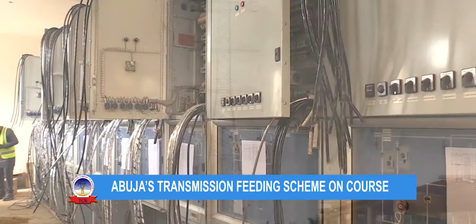An assistant manager at the AIFDPIU of TCN, Engineer Mohammed Zubairu, gave an overview of the Gwarimpa gas-insulated substation project, which he supervises. The station is 2 by 60 MVA, meaning it has 2 transformers each of 60 MVA capacity, and it has 6 feeders that radiate to the distribution unit.